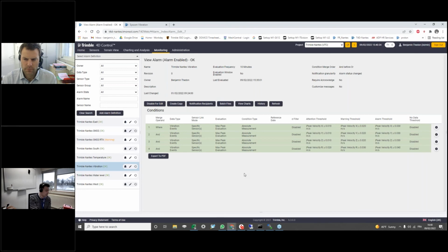This is why the sensor itself has to manage the alarm, but we also have a way on T4D to manage the alarm. For example, when you raise an event with the sensor itself, you are able to receive an email, or the customer will be able to receive an email also. Here we put different levels of alarm on different components, on X, Y, or Z. And you can also create an alarm if you don't have data for hours or days.